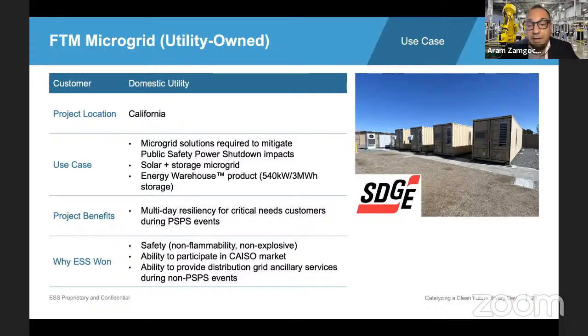So why are they working with us? Well, one, the safety aspect. The battery is non-flammable, it's non-explosive. Two, because the battery doesn't degrade, during non-wildfire season in the state of California, the utility is going to operate the battery to participate in the CAISO market to accelerate the payback period.